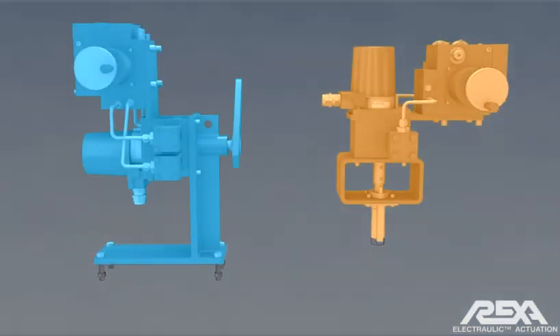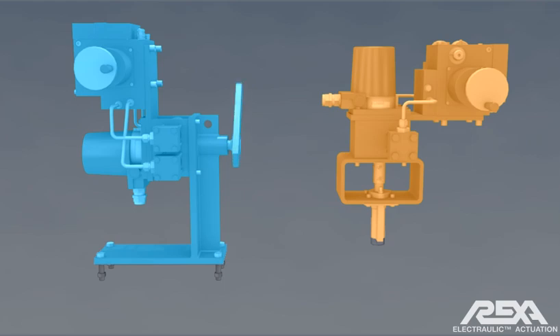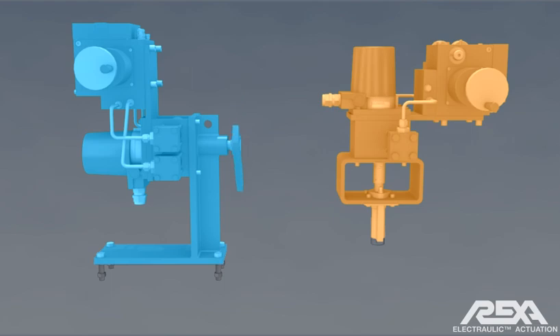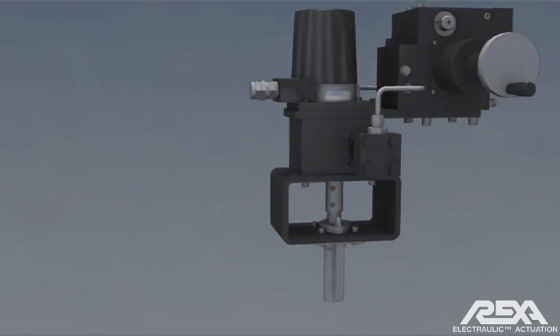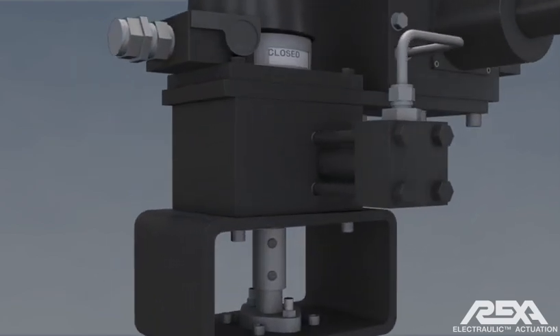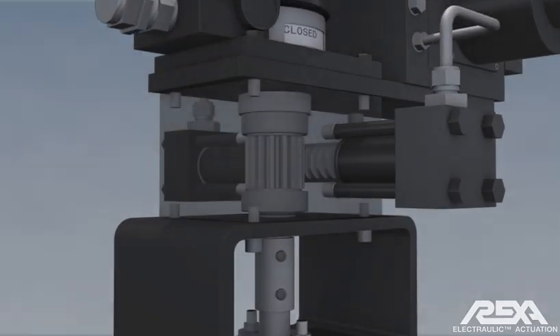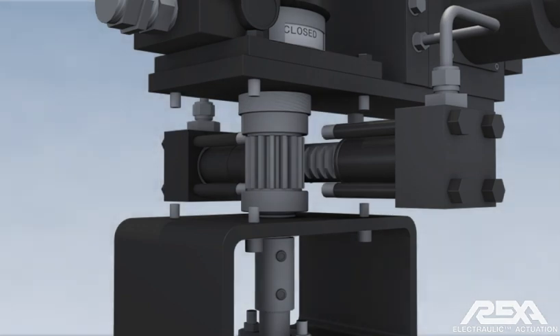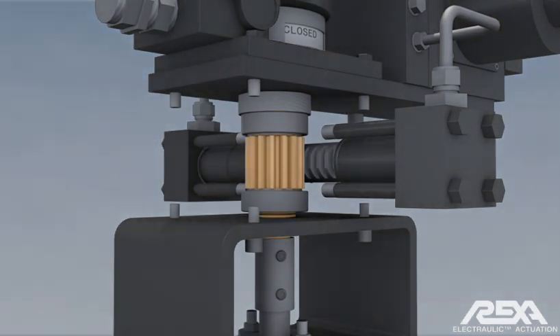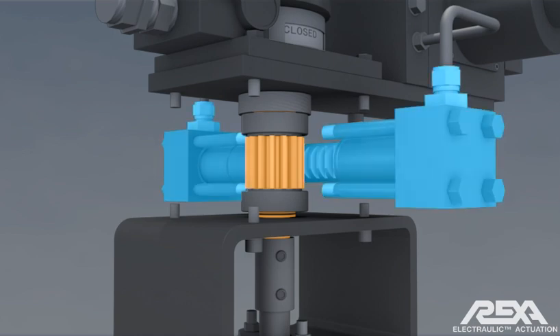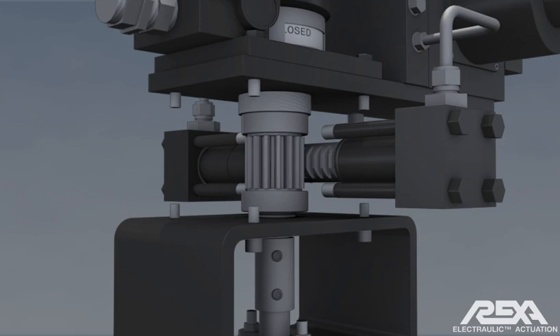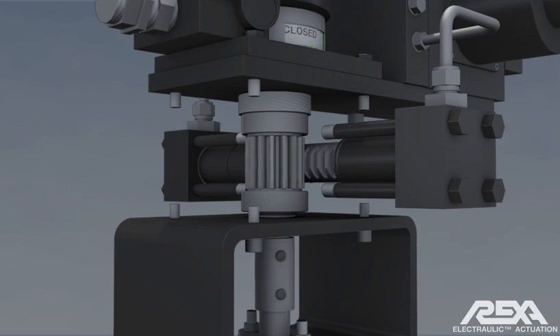The rotary and drive actuator provides a 90 degree movement for use in ball valves, butterfly valves, or dampers with linkage. The attached valve or drive arm will be connected to a pinion, which is turned by a single or multiple racks. Hydraulic pressure at the ends of the rack will provide the movement.